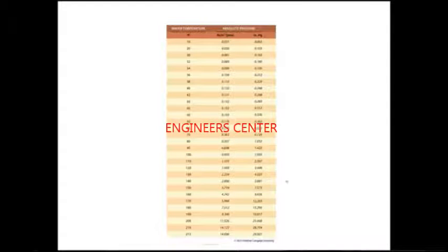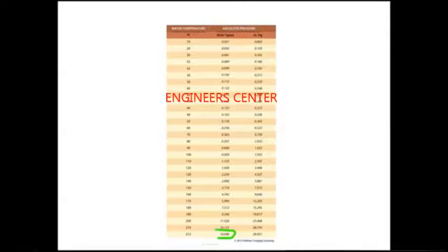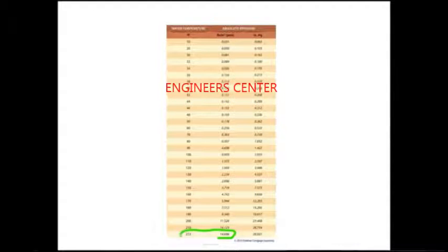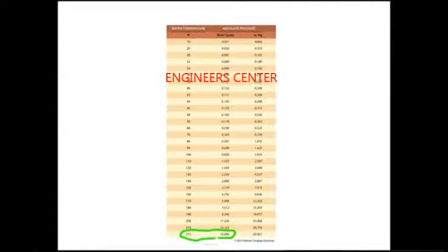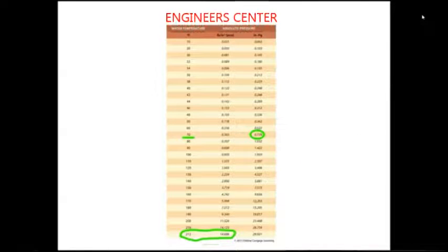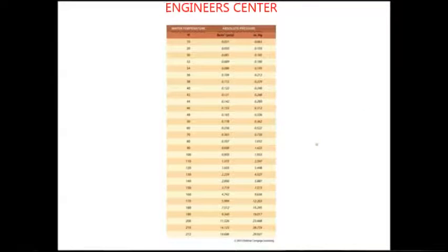So this is a pressure temperature chart, or PT chart, for water. And we have these charts for refrigerant as well. But let's look at this. This is atmospheric pressure down here at the bottom, 14.7 psi. And at atmospheric pressure, water will change state at 212 degrees. Now, let's say we reduce that atmospheric pressure and we put the water into somewhat of a vacuum, we can change the state of that water at 70 degrees Fahrenheit. And the same thing happens if you increase the pressure, and it increases the temperature that the water changes state.